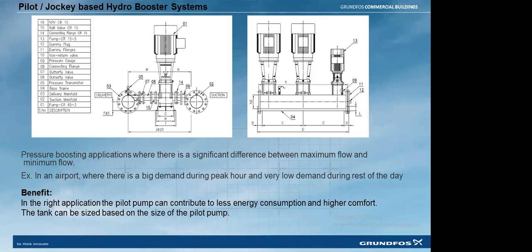In that case, you will still ensure a better system efficiency, because even if you are operating a pump on a VFD, when the load goes below 25%, the efficiency of the pump and the overall efficiency of the system will come down. To eliminate that issue, we can have that pilot pump. When there is a reduction in the flow rate below 25%, that requirement automatically shifts to the pilot pump to take care of the minimum flow requirement.